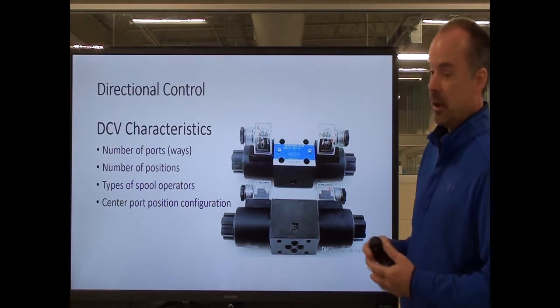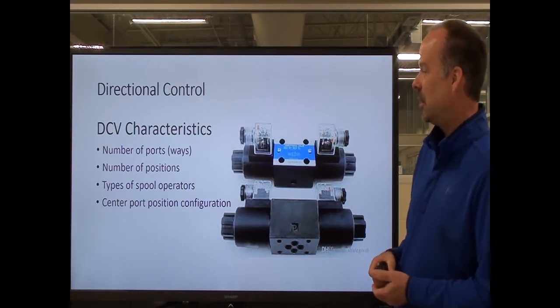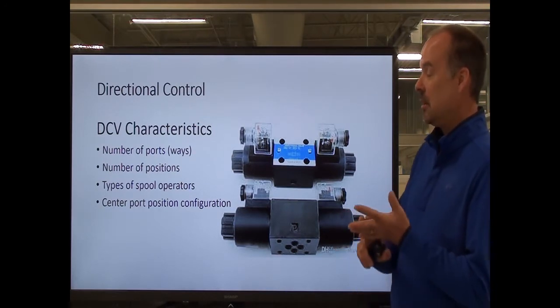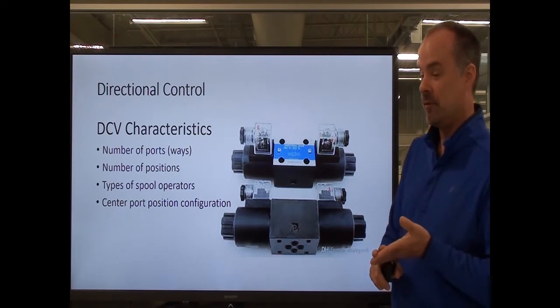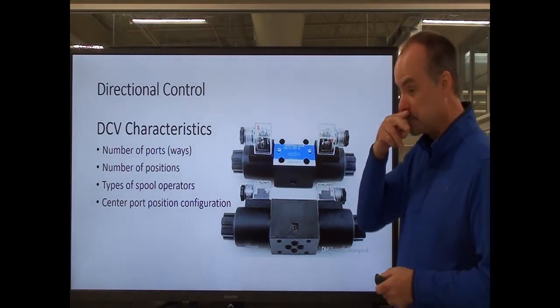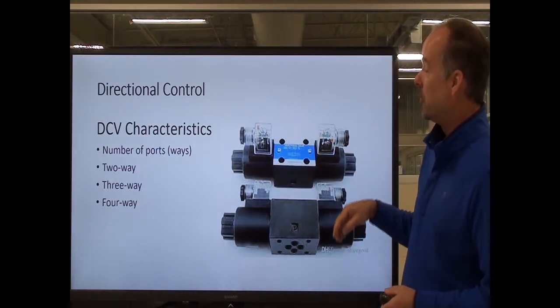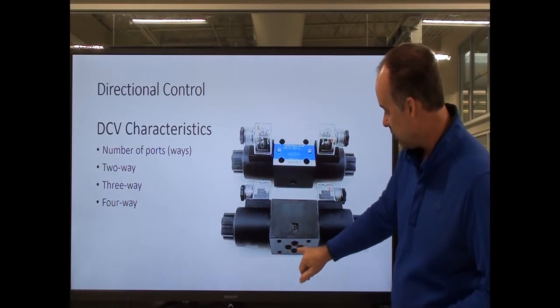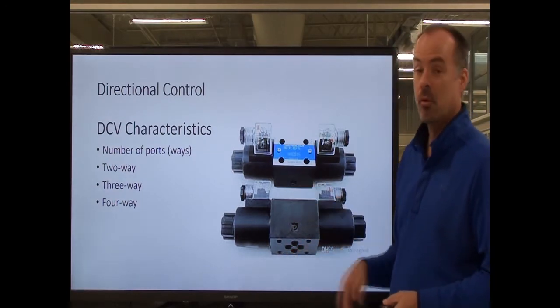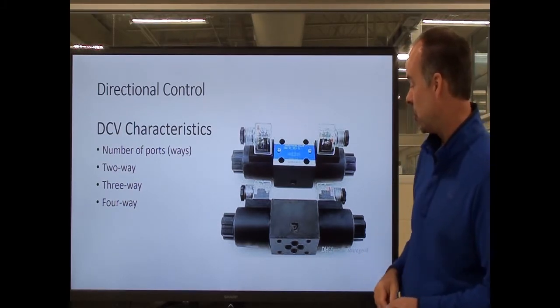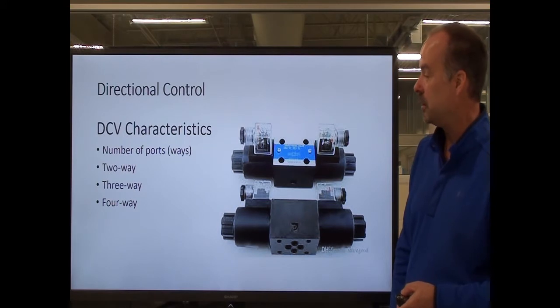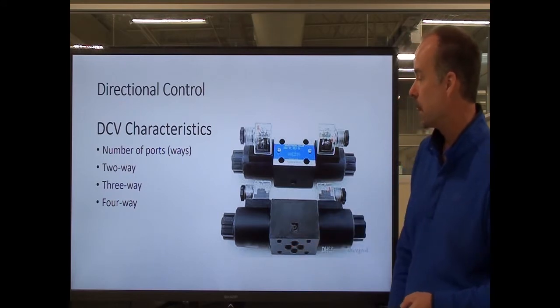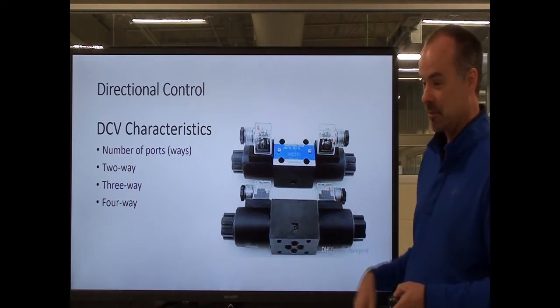Valves are named using a naming convention based on the number of ports or ways, the number of positions, the types of spool operators, and the center port configuration. Looking at the bottom of this valve, I can see four holes, which tells me it's a four-port or four-way valve — meaning there are four places for fluid to flow. Some valves could be two-way with only two ports, or could have three.